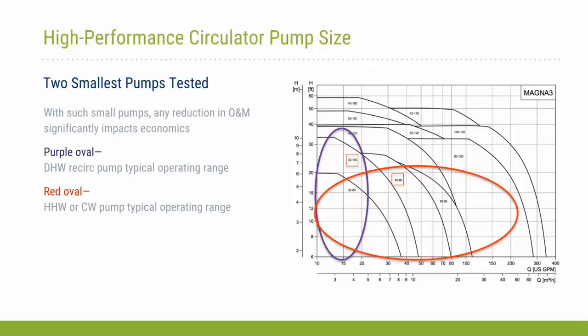When we started this demonstration, the smallest pump that was manufactured was the 4080 that's listed there. And then about halfway through, they re-released the 32100 and 3260 pumps. And as you'll see in the next few slides, we're testing these on the smallest pumps that were available. So when we started the demo, we started with an evaluation of the 4080, and then about halfway through moved to the 32100. One thing I would note is for domestic hot water recirculation pumps, especially in high-rise buildings, you're essentially pumping a small amount of fluid up to the top of a facility, and so those typically tend to be dominated with high head pressure and low flow rate. It's a very challenging point on the pump curve for these pumps to operate at.